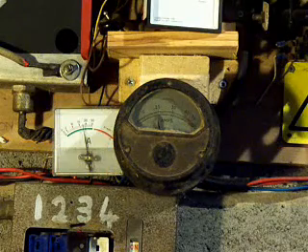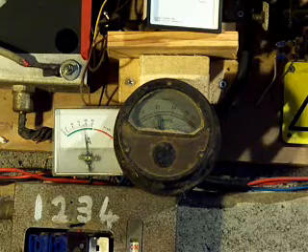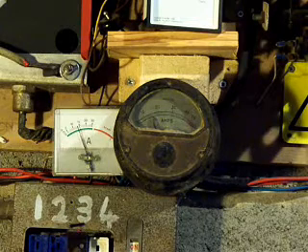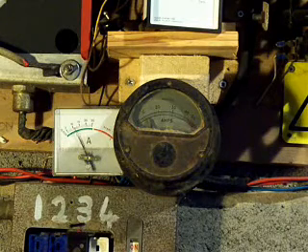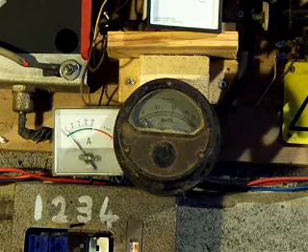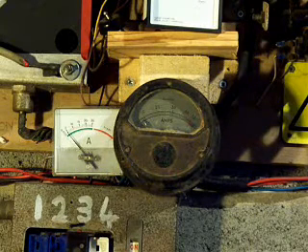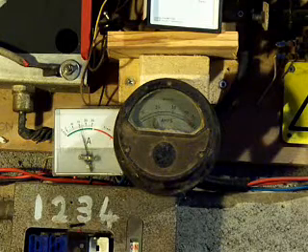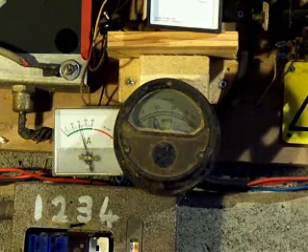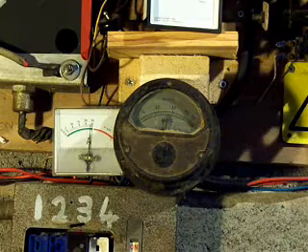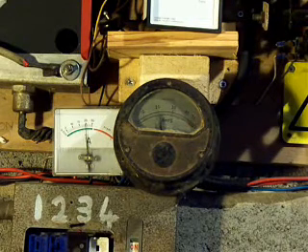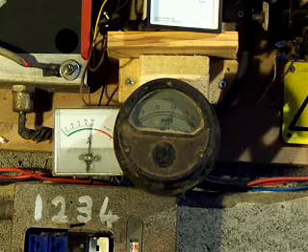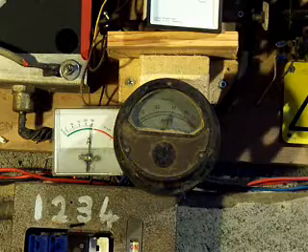It's an exceptionally windy day. I just thought I'd bring the camera in here to show you the ammeter, how it fluctuates. See there, it's about 20 amps, down to 10, when the wind gets up it'll go above 30. If it's charging at 20 amps on a 48 volt system, let's call it a nominal 50 volts, 20 times 50, 2 5's 10, that's 1000 watts. That's a kilowatt. So when it gets to 30, it's a kilowatt and a half.